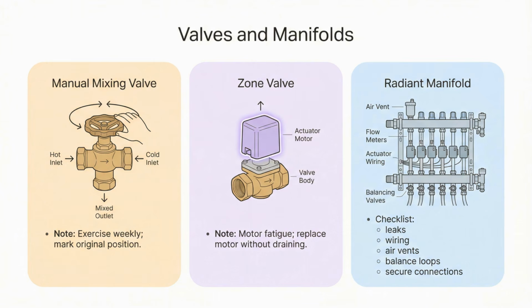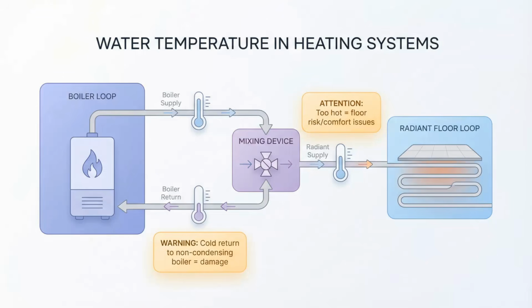Manifolds may need periodic checks for leaks, secure wiring to actuators, working air vents, and balanced loop flow, especially if occupants report hot or cold spots. Water temperature needs to be checked throughout the system. Cold return water to a non-condensing boiler can cause unnecessary damage and lead to failure. At the same time, the boiler supply must be hot enough to satisfy all loads, and the radiant floor supply must be controlled so it's not too hot entering the floor circuits, both for system protection and comfort.